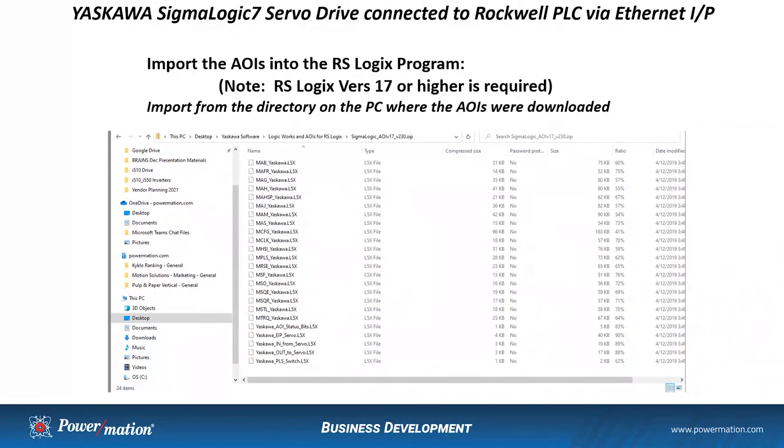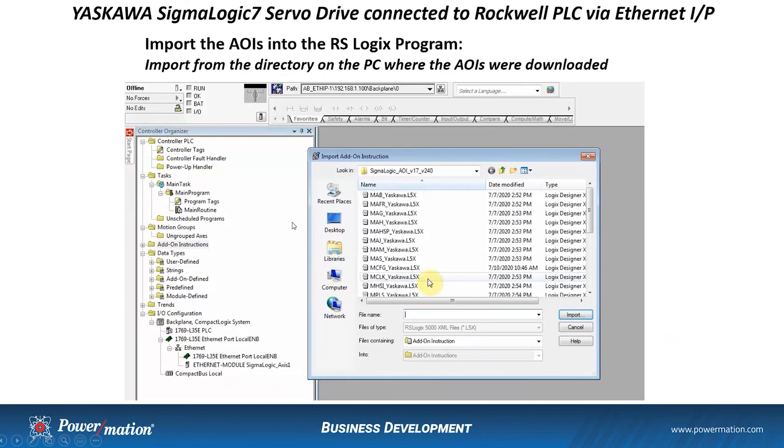Now that we have our SigmaLogic7 servo drive configured and tested with the Logic Works software, we'll move to the PLC side. First, we're going to import the AOIs into the RSLogix program. Please note that RSLogix version 17 or higher is required to work with the Yaskawa AOIs. I've shown the directory on the PC where I downloaded the AOIs. From the RSLogix software, we do the import AOI function and point to that directory to bring them into our RSLogix program.